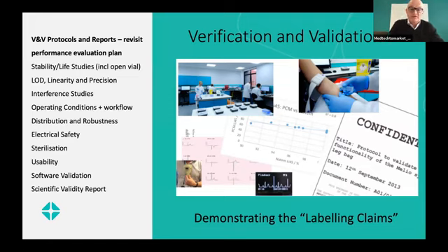Stability life studies, so that might be study an instrument, and in fact one of those big differences between those 2 glucometers is the decontamination and the life expectancy of those instruments, because one of those isn't so robust to repeated wiping, which is why it's single operator only, because you don't have to worry about cross-contamination of blood. So you have to do life studies to demonstrate your instrument or your electronics are up to the repeated use.